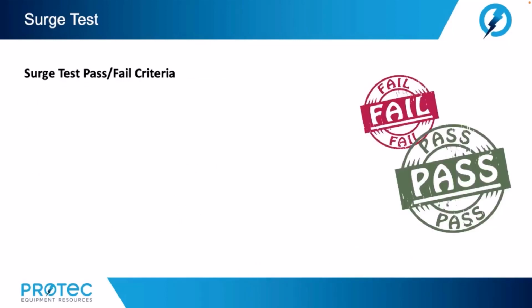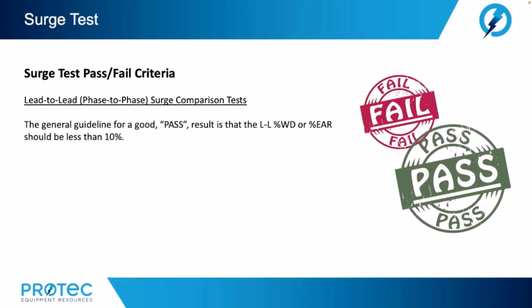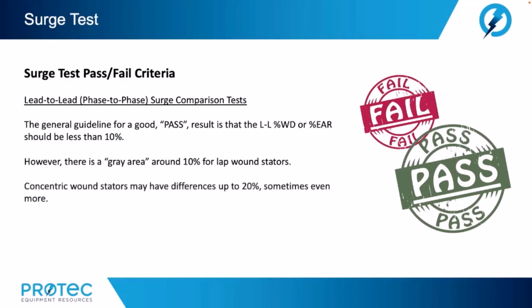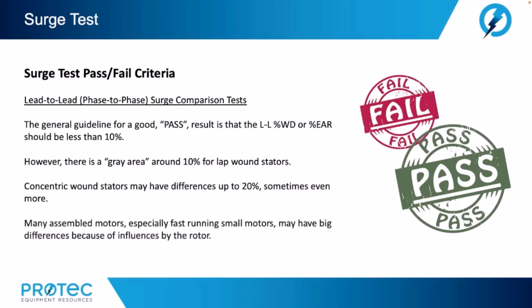Which brings us to the surge test pass-fail criteria. Lead-to-lead, phase-to-phase surge comparison tests. The general guideline for a good or pass result is that the lead-to-lead percent WD or percent EAR should be less than 10%. However, there is a gray area around 10% for lap wound stators. Concentric wound stators may have differences up to 20%, sometimes even more. Many assembled motors, especially fast-running small motors, may have big differences because of influences by the rotor.